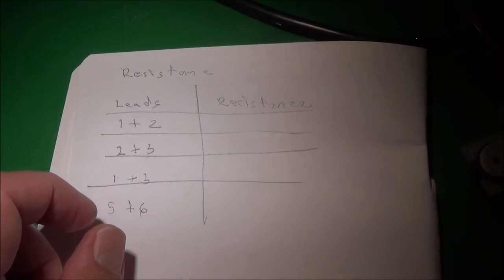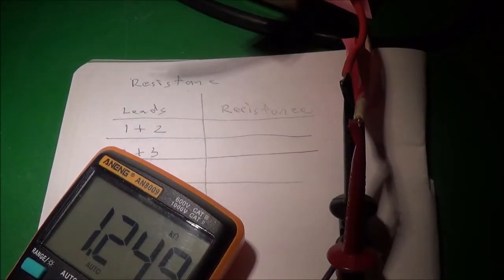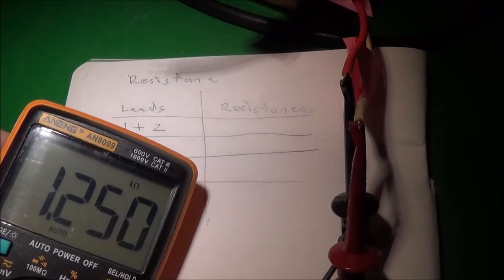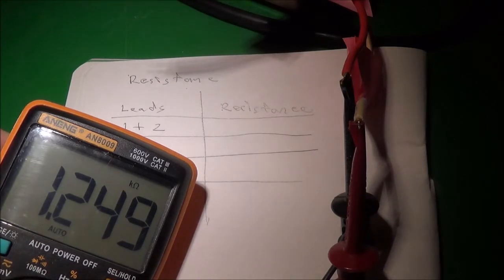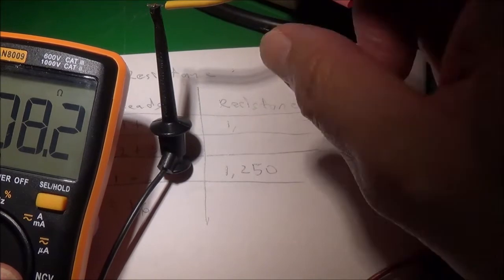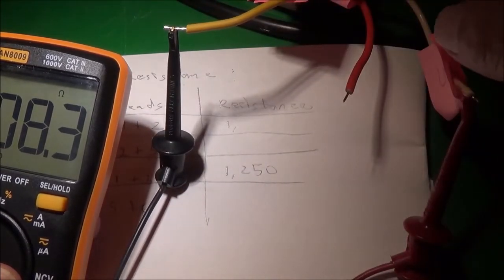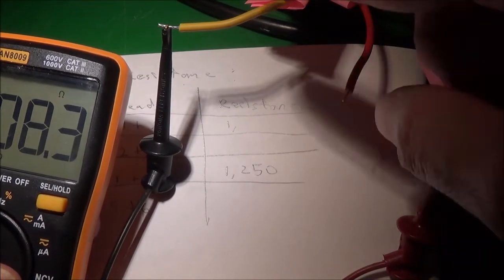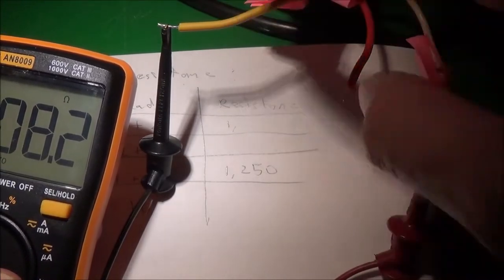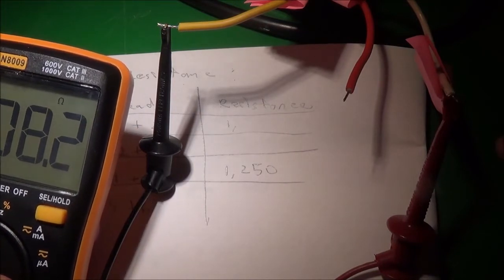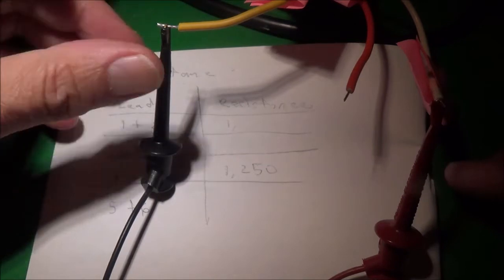Before I start, I made myself a little chart here. It's not pretty, but it'll do the job. See here leads, resistance between lead one and two, two and three, between one and three, and then five and six. So right now I'm measuring between the leads one and three, which is the white and the red. And here I've got 1250 ohms, you can say, or 1.25 K.